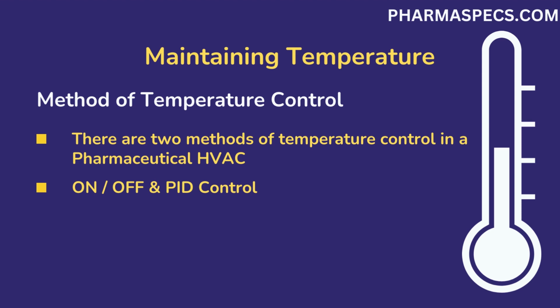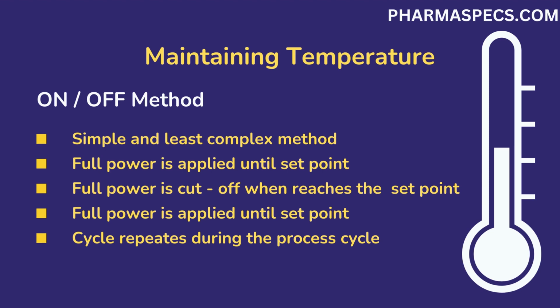There are two methodologies to control the temperature through pharma HVAC. One is on-off and the other one is PID control method. The on-off method is the least complex. It requires simple control components and logic to execute the temperature control system. It works by applying full power until the temperature reaches the required value. Similarly, full power cuts off when temperature reaches the required value. The on-off cycle repeats itself throughout the entire production process.